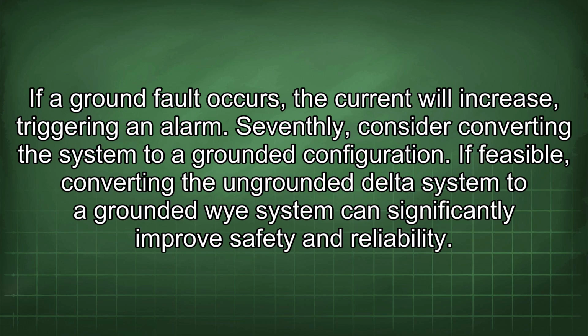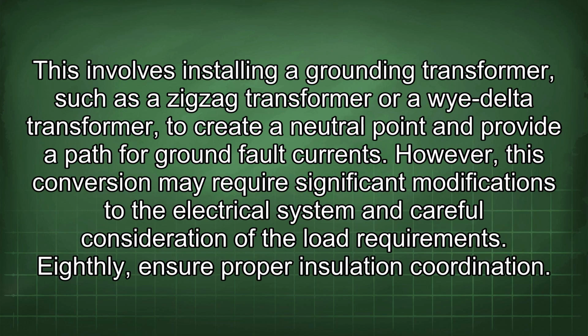Seventhly, consider converting the system to a grounded configuration. If feasible, converting the ungrounded delta system to a grounded Y system can significantly improve safety and reliability. This involves installing a grounding transformer, such as a zigzag transformer or a Y delta transformer, to create a neutral point and provide a path for ground fault currents. However, this conversion may require significant modifications to the electrical system and careful consideration of the load requirements.